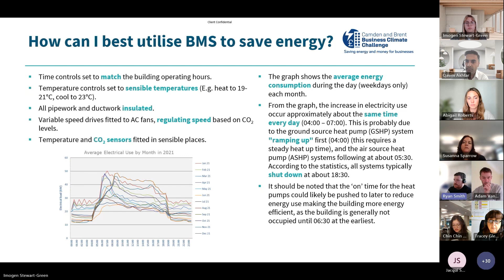Yes, so this is an organisation that optimised their controls. So in 2021, Reed House, a 3-storey office complex, approached us to upgrade an existing obsolete site-wide BMS system. To achieve maximum energy saving, an approach was taken to rewrite the control strategy for the building and install new software. So all existing plant controllers were swapped out for new controllers with a new demand-driven software installed across the whole site. So multiple PIR detectors, again, what Imogen was talking about earlier, and new CO2 monitor sensors were installed to monitor conditions in the offices, and this allowed the main ventilation plant and fan coil units to be run at a setback temperature if areas were unoccupied, while maintaining good indoor air quality conditions at all times.